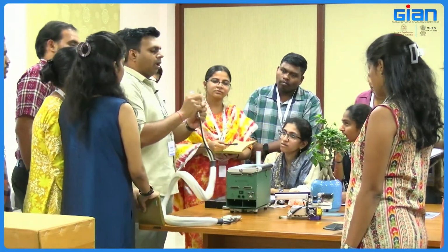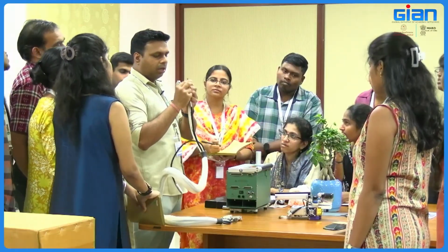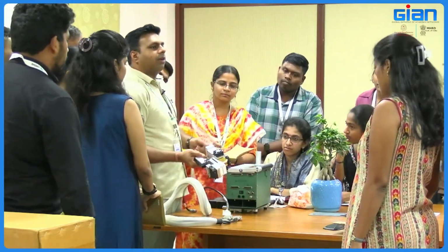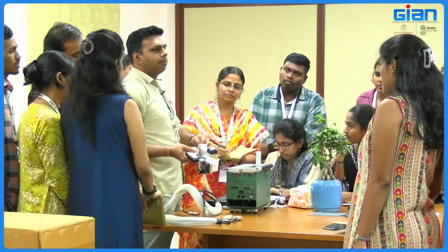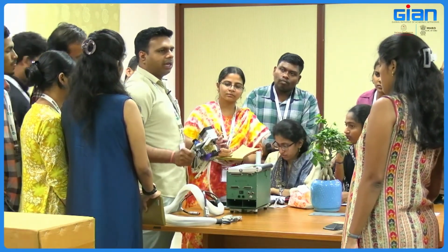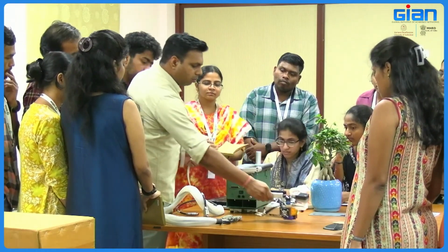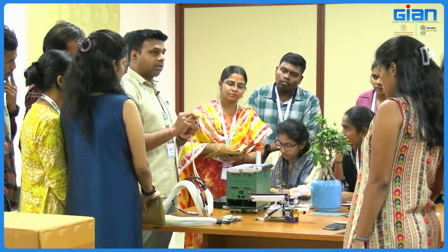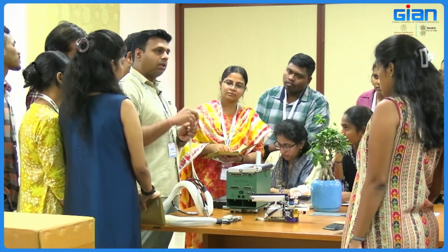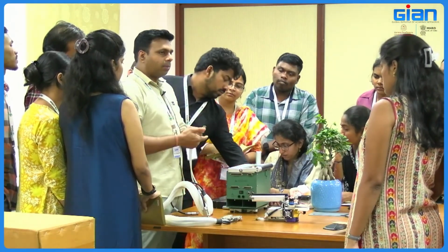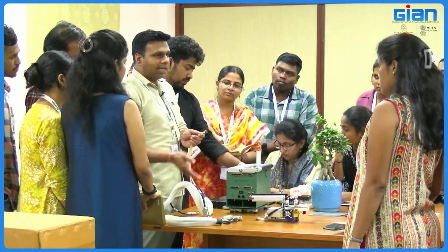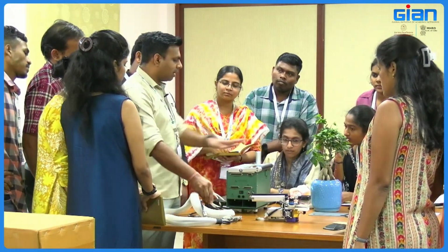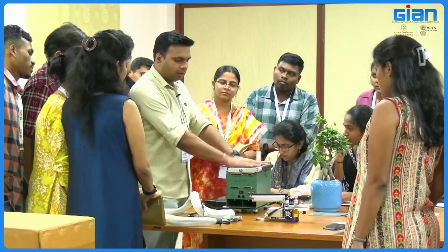So here you see there is a black colored mark. This black mark has to be matched up with this black. Otherwise, if you mix up the reference with the sample and the sample with the reference, all readings will come out faulty. So the first thing you have to do is fix it. Another thing is that once these gaskets are damaged, you have to replace them, because if you do not replace them, the CO2 will leak, and once there is leakage, again the readings will come out faulty. So by the time he fixes it, I will tell you exactly what this fix is.